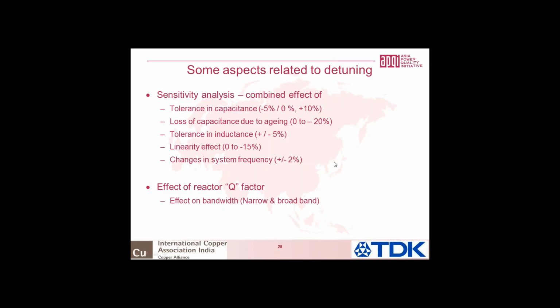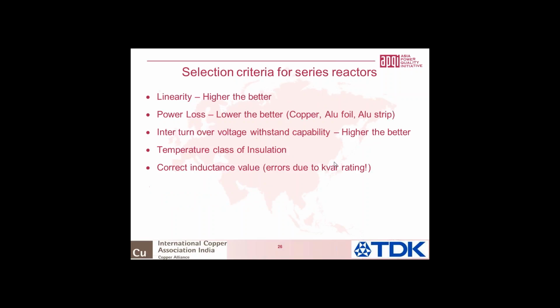Now let me quickly run through two or three slides. Apart from these factors, we also look at the linearity of the reactor, higher the better, and power loss, lower the better. India today still has a tendency to buy aluminum wound reactors, be it aluminum foil or aluminum strip, which will have at least 50-60% higher loss than copper. So here a copper wound reactor would have a lifetime benefit rather than an initial capital cost.